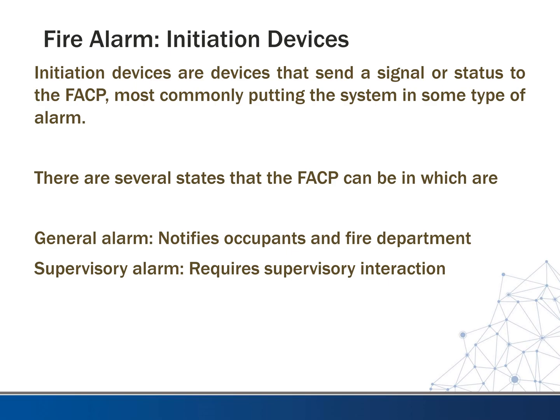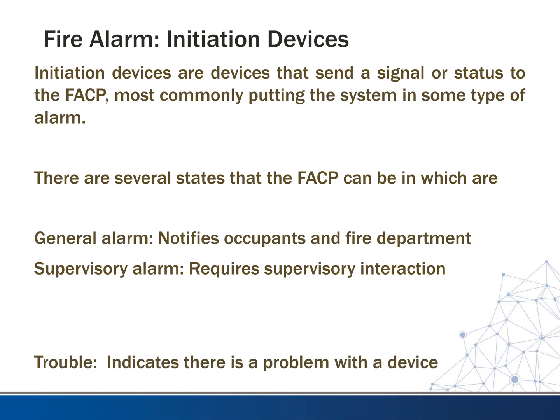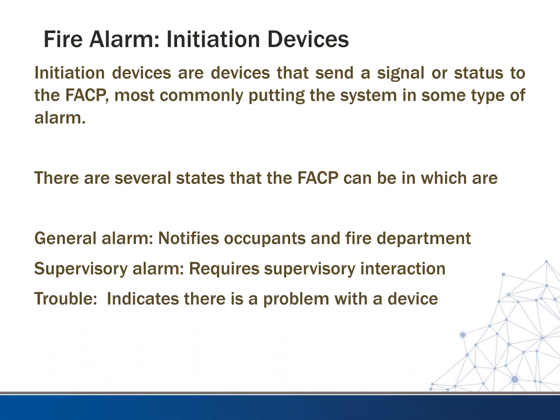This approach tries to avoid nuisance alarms that you sometimes get in hotels. Another state the fire alarm control panel can be in is a trouble state, which indicates there's a problem with the device. Many fire alarm devices have self-diagnostics — they'll test themselves, and if they don't pass or detect something out of spec, they'll send a signal back to the fire alarm control panel to indicate something's not right.